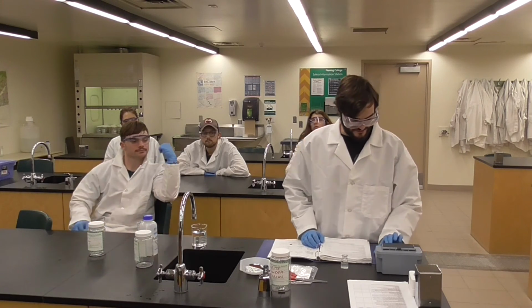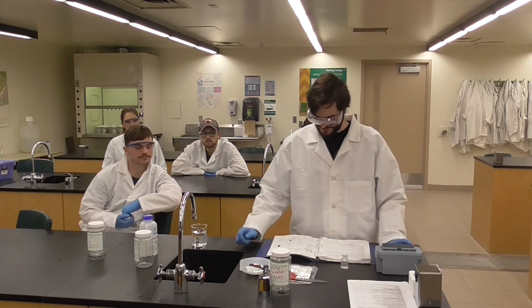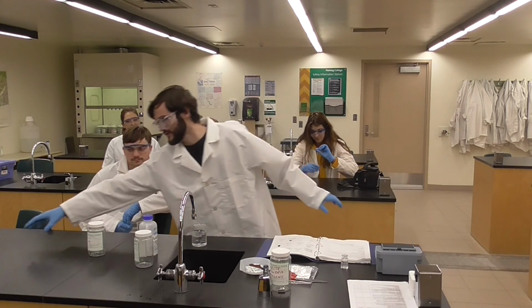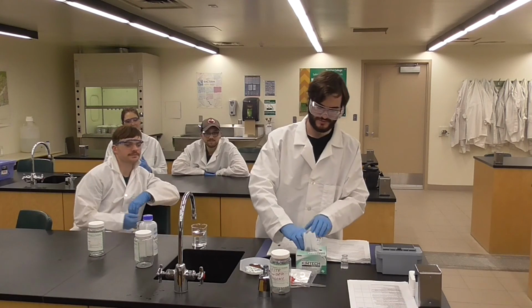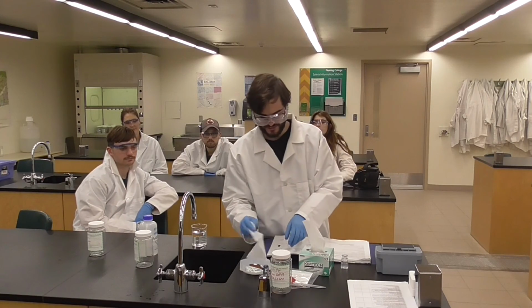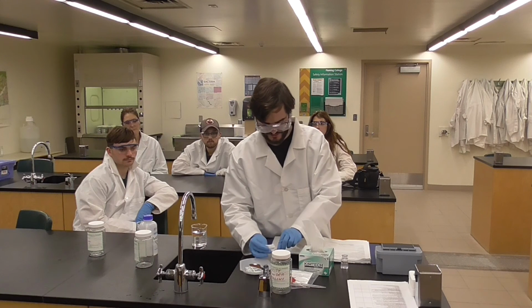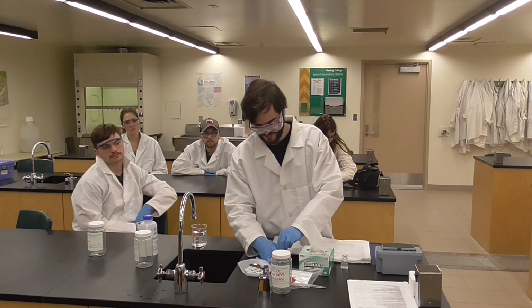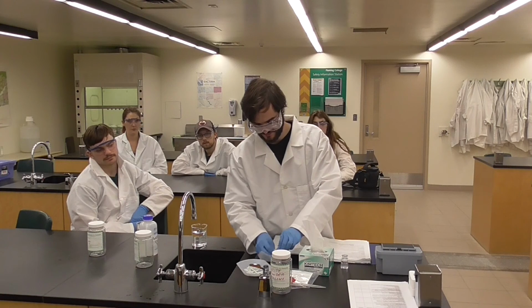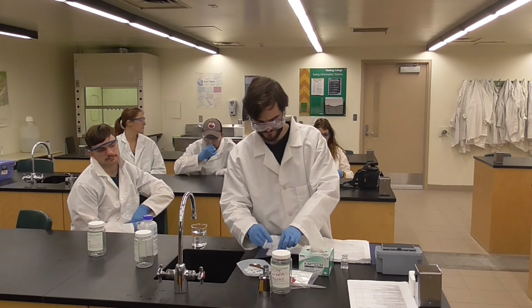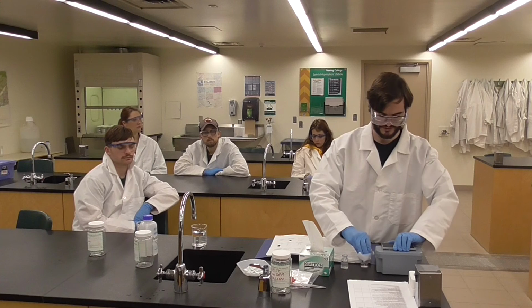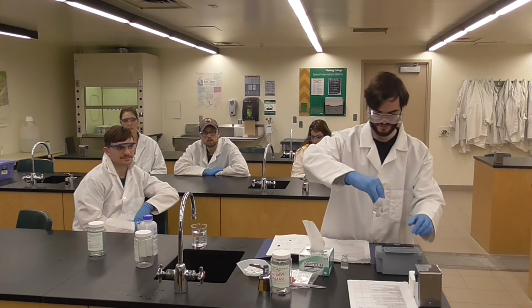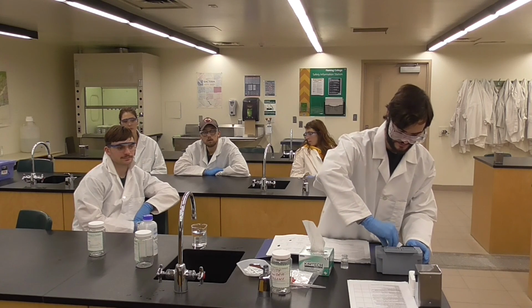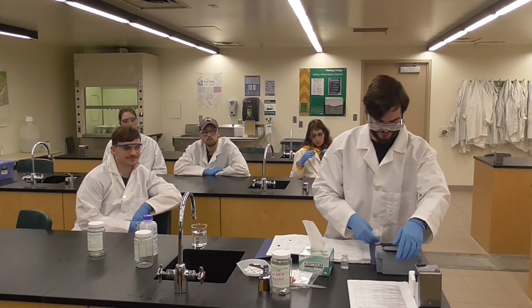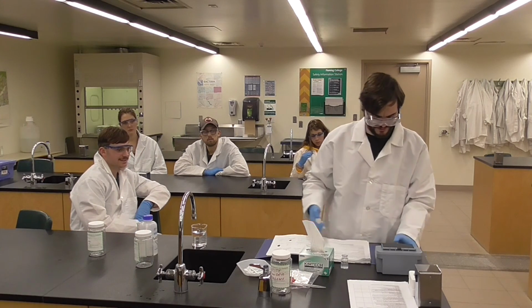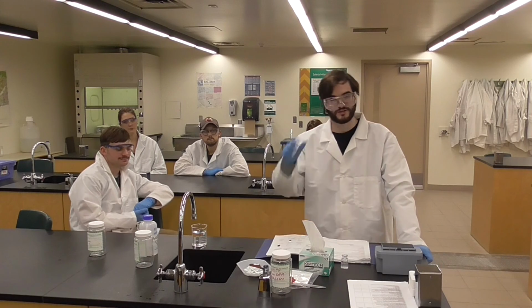Alright, so our timer's just gone off, so let's stop that because it's annoying. And then we'll grab some Kim wipes. And we'll wipe off our blank cuvette with that so that there is nothing on the outside of the glass that is going to interfere with the spectrophotometer. And then open up the lid and place that in with the fill line to the right. Like that. And then make sure the lid is closed, and we're going to zero the instrument off of that blank.